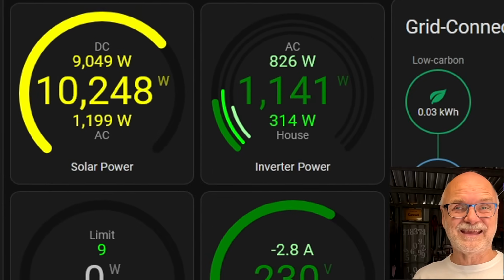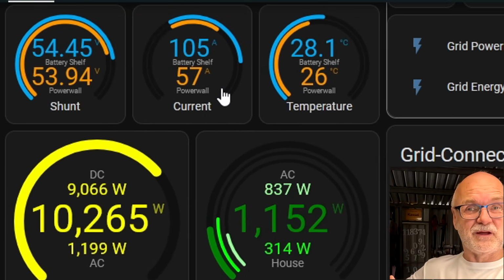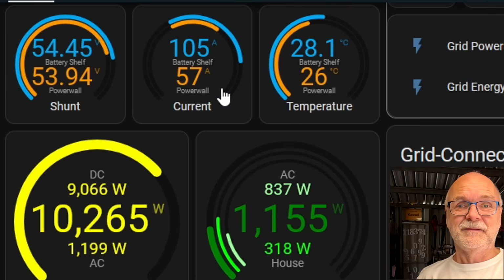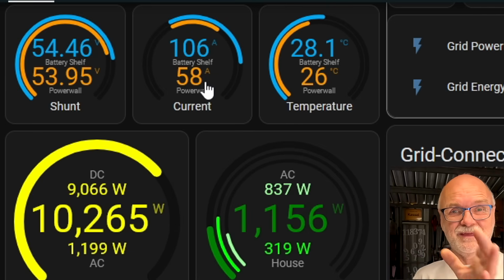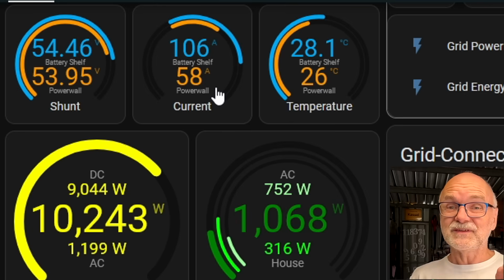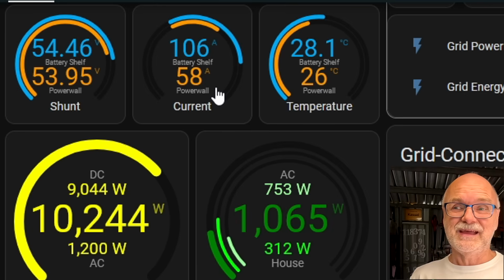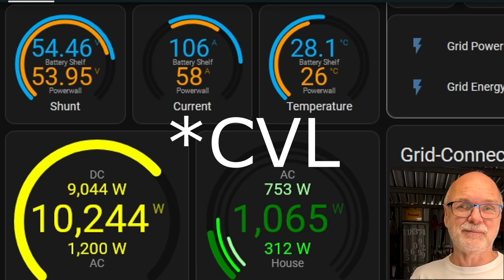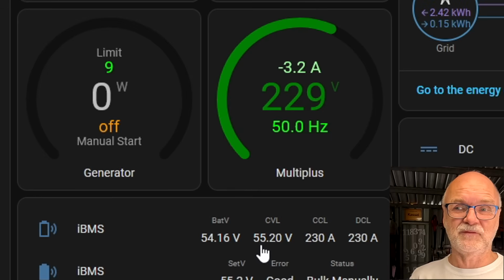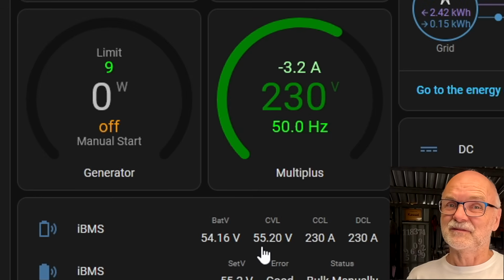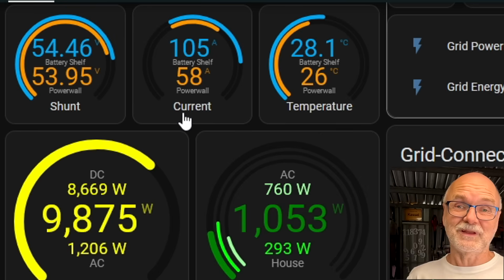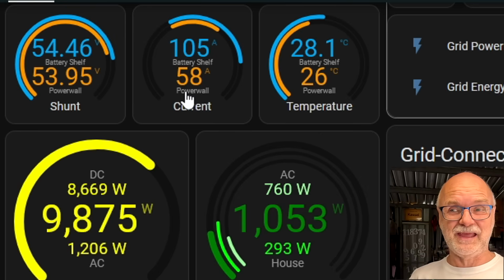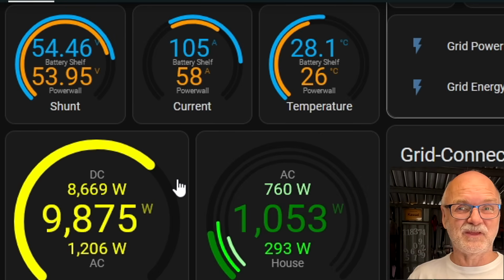I look at the current going through this 63 amp circuit breaker, which is what we're measuring with the second shunt, going into all the batteries in the Powerwall. If this current goes over 60 amps, I reduce the CVL by 0.1 volts, so it goes down from 55.2 to 55.1. I check this every 20 seconds. If the current is still too high, over 60 amps, I reduce the charge voltage again by 0.1 volts. Once the current goes under 60 amps, like now at 58, the automation pauses and nothing happens.